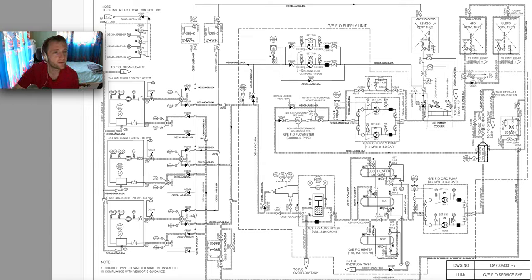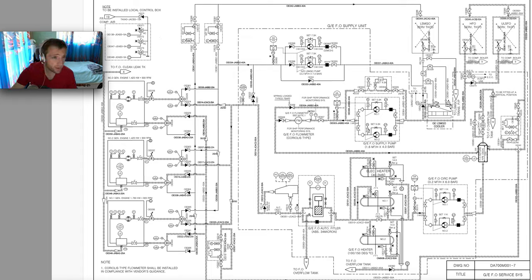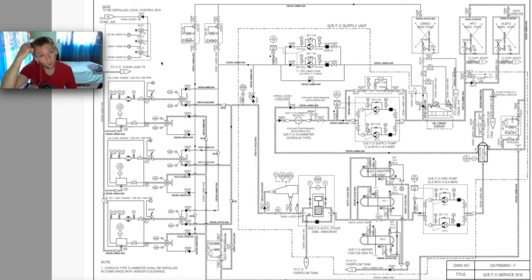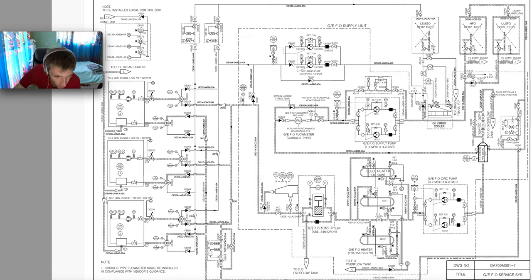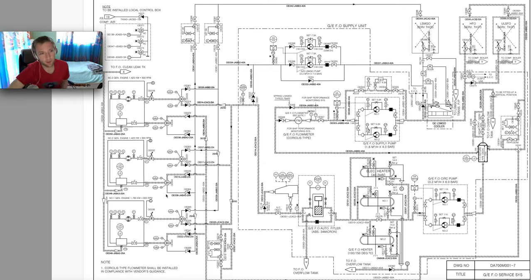There is always a supply of compressed air here to the line — it is always under compressed air. When we turn this local valve, we depressurize the line and our quick closing valves will close. This is how it works. Also, this quick closing valve must be tested when the generator is not running and must be lubricated with some kind of penetrating oil.